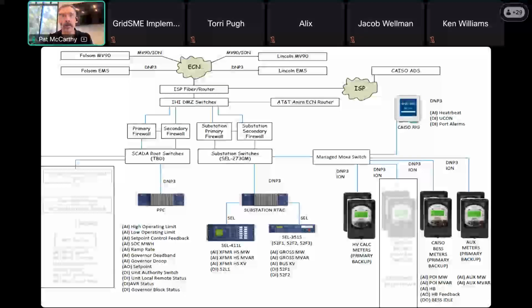You're going to need to either inject voltage and current to produce real measurement output from those devices, or you're going to have to know some fancy tricks about how to simulate from the device through that SEL protocol I have on the screen, through the intermediate device and up to the RIG. I'm mentioning that specifically because that push is kind of new from CAISO—it didn't used to be normal to have substation test equipment as part of a point-to-point test. It can mostly be done through fancy tricks with forcing data depending on your relay devices, but that's new space. Make sure you either know how to do it or have your relay test techs on site to perform injections.